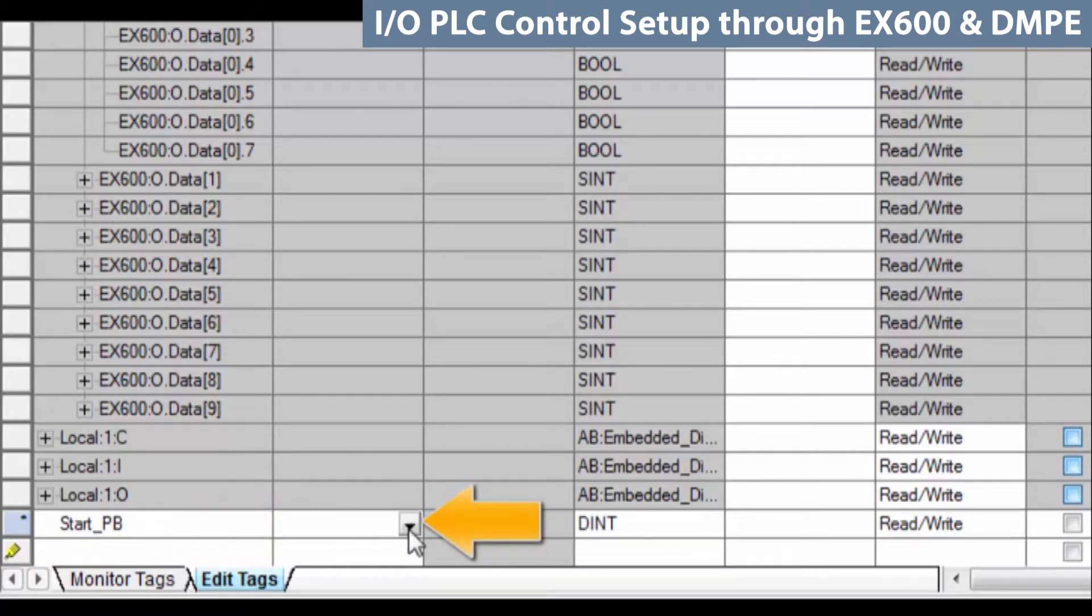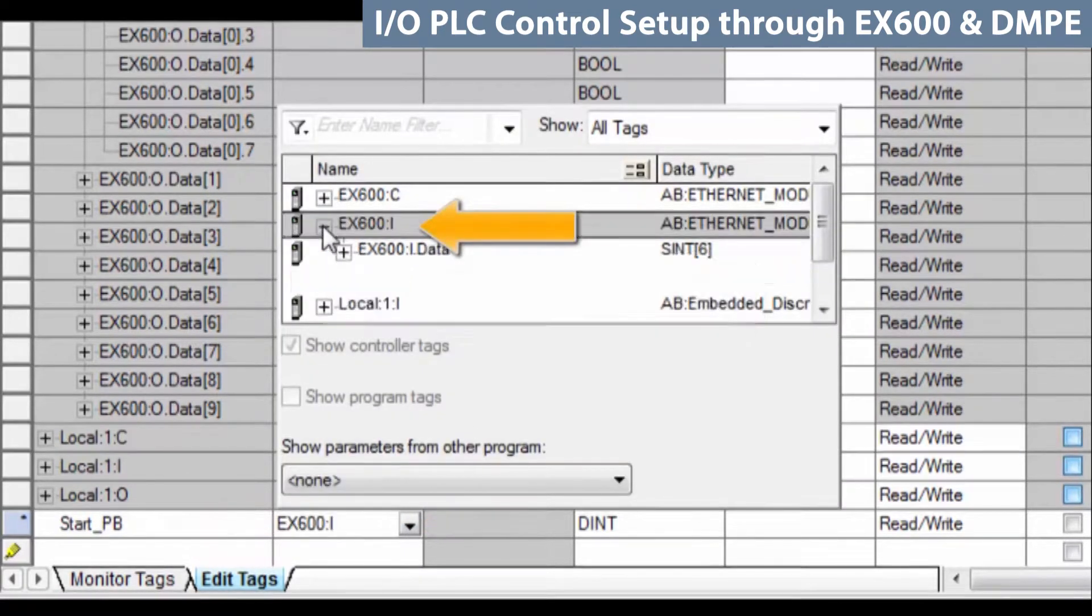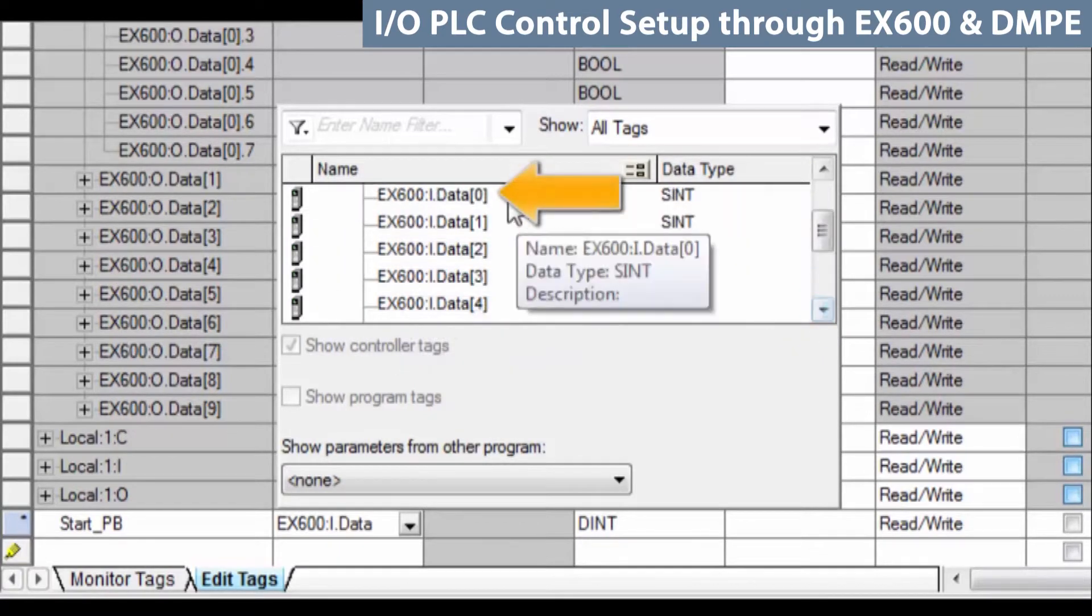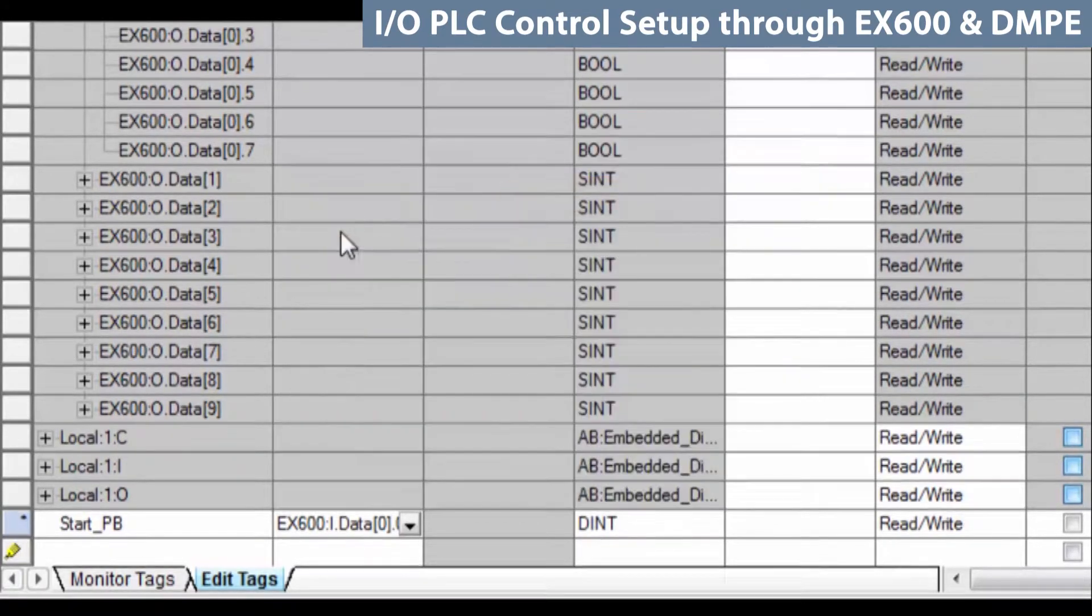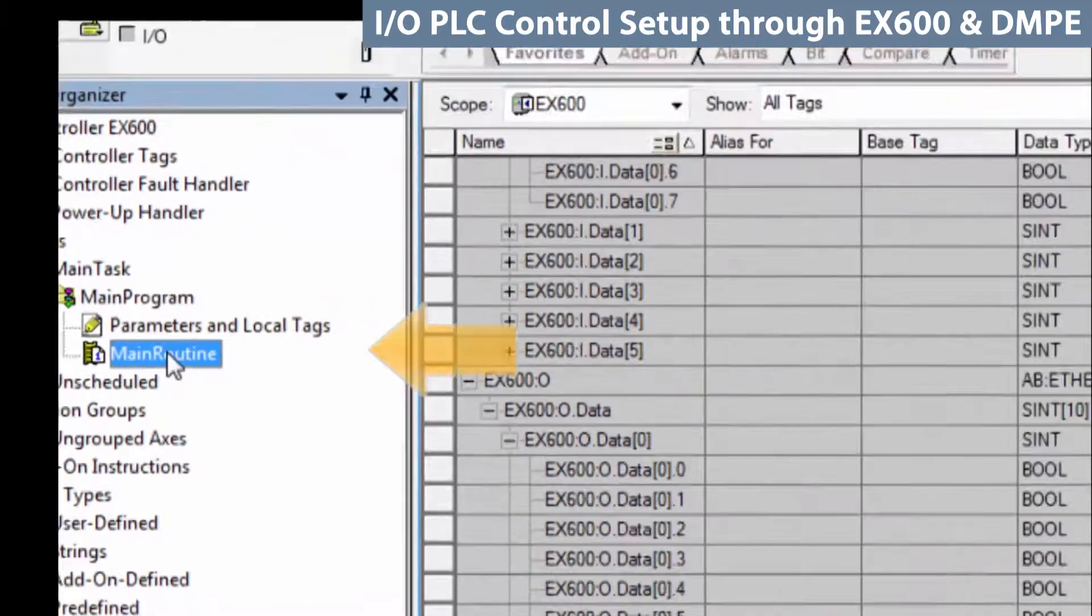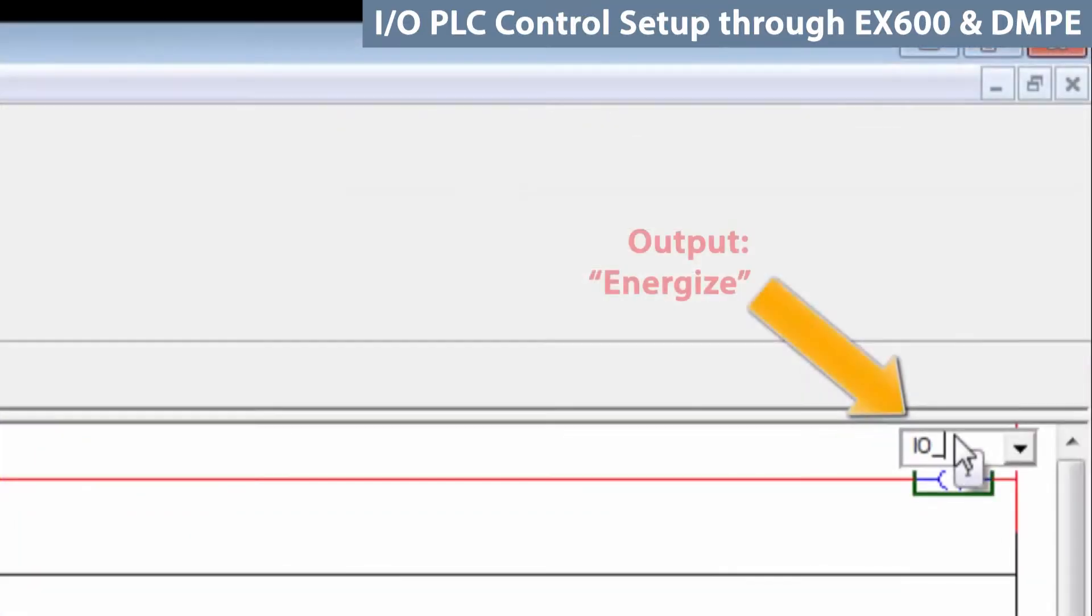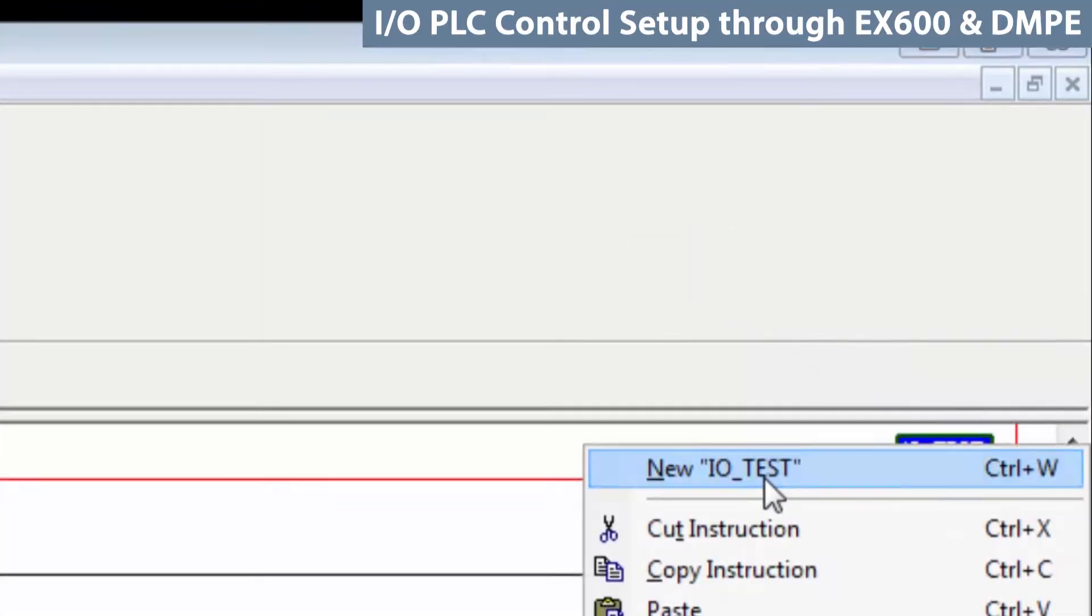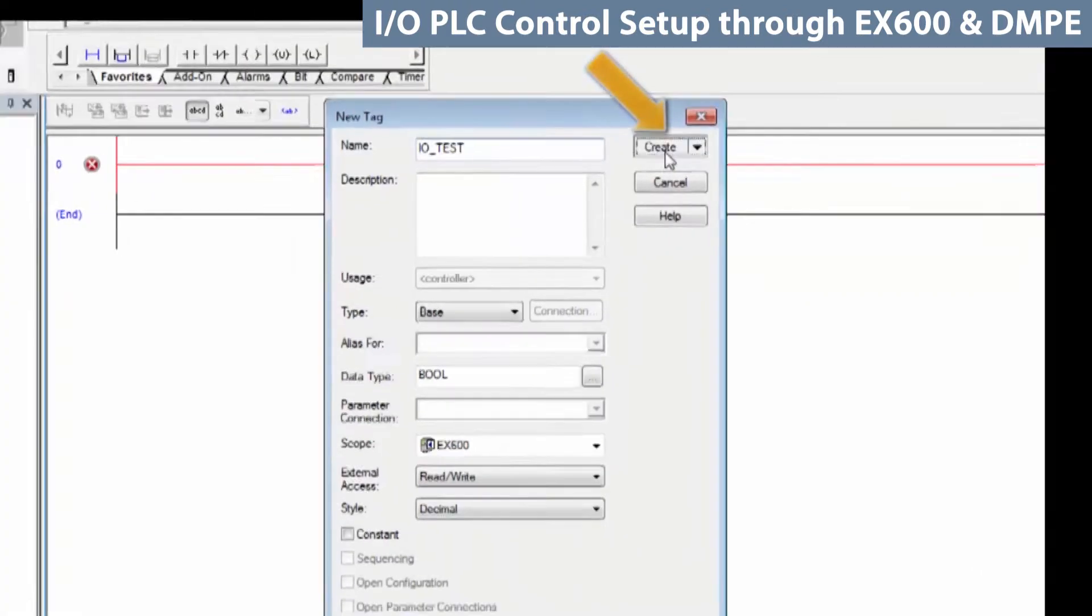Begin with the start push button. Select input data 0, bit 0, give it a name and then an alias. Then, go and create a rung for I/O test. To do that, go to the main program, go to the main routine. First, we create a dummy bit for an output called I/O test. Right-click on it, select new, and create.